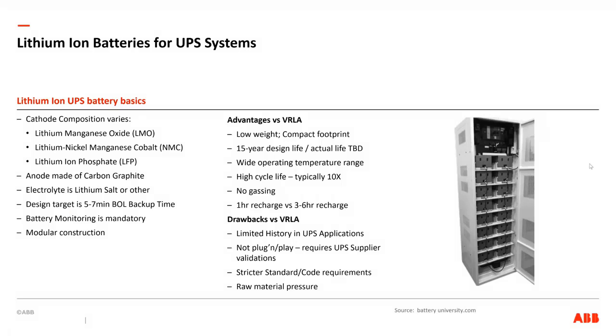But on the benefit side, the reason a lot of people are interested in using lithium ion batteries is that they're compact. They're very light. Weight is often a quarter of an equivalent VRLA. They're typically less than half the footprint, and footprint is expensive. The design life for most of the manufacturers, and there are a number of companies making lithium-ion batteries, is 15 years. And you can usually get a 10-year warranty on that 15-year battery.